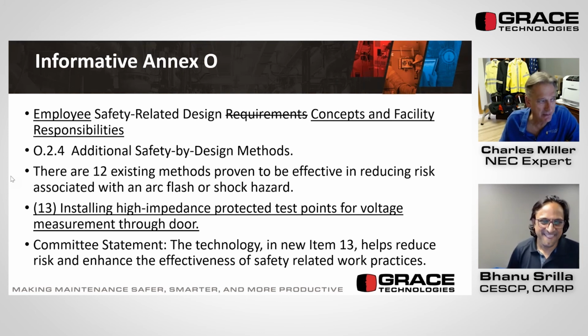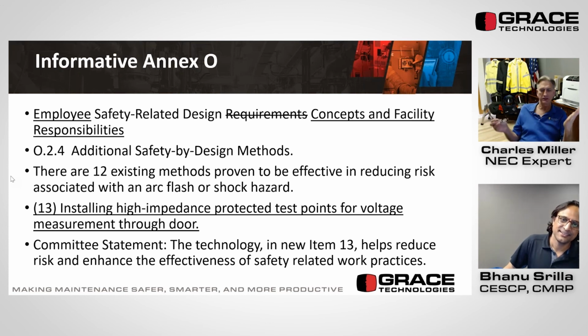And what's coming to the equipment has to be less than the equipment is rated for. But determining that for an electrician or maintenance person, we're just asking for trouble. Now what this does is it will never let you turn a breaker or switch on or off without being completely suited up if your equipment is not in normal operating condition. Yep, I think that's huge.